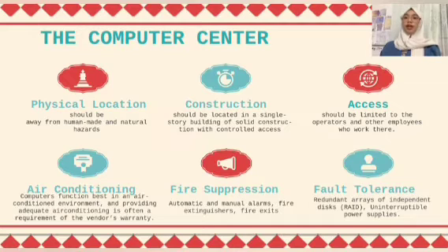Next one is the air conditioner. Computers function best in an air-conditioned environment, and providing adequate air conditioning is often a requirement of the vendor's warranty. Computers operate best in a temperature range of 70 to 75 degrees Fahrenheit and a relative humidity of 50%.